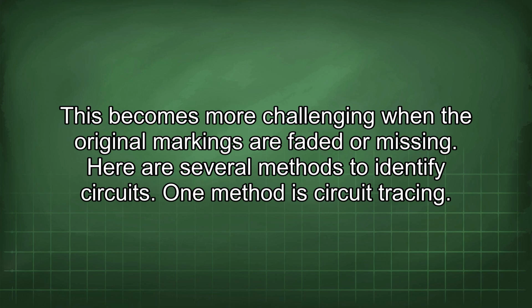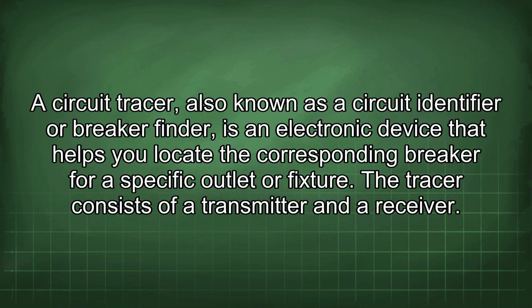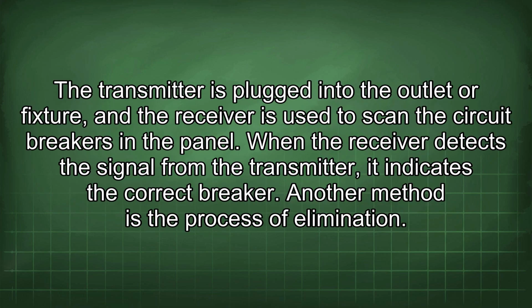One method is circuit tracing. A circuit tracer, also known as a circuit identifier or breaker finder, is an electronic device that helps you locate the corresponding breaker for a specific outlet or fixture. The tracer consists of a transmitter and a receiver. The transmitter is plugged into the outlet or fixture, and the receiver is used to scan the circuit breakers in the panel. When the receiver detects the signal from the transmitter, it indicates the correct breaker.